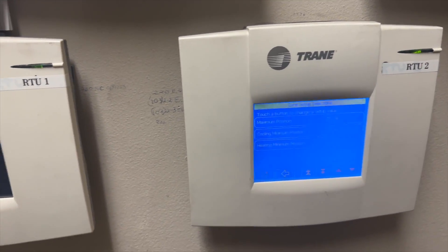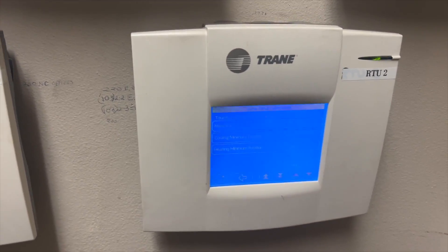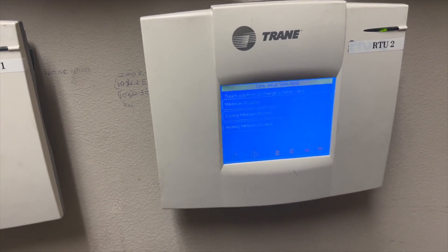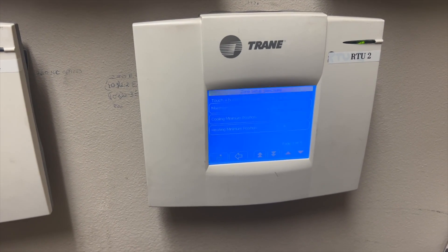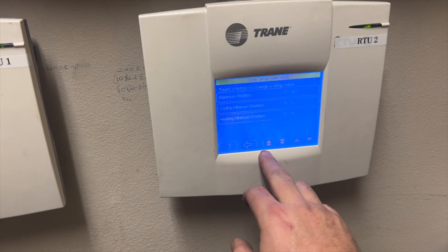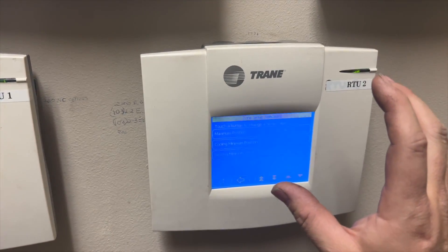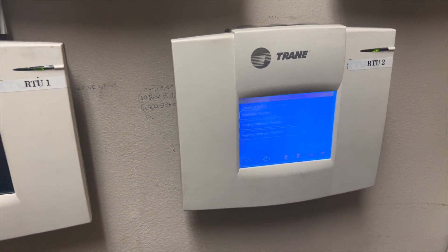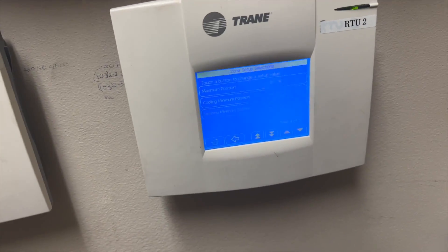We tried 36 but I just went 37 to give it a little extra. He's probably going to have some heating and cooling issues, but he's a therapist and needs it quiet in there. I already told him it's a compromise and we'll have to find a sweet spot. I was looking at the ductwork and the main trunk runs right there with just a short duct running right into it, so we're hearing the friction of the air moving inside the duct.